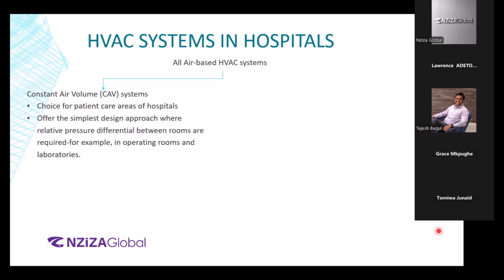The design is very simple. You don't need to have many transitions in the ducts going up and down. The coils are pretty straightforward because it is a constant volume that you'll be pushing through the system, right? And on the other side, we have the variable air volume, right? Variable air volume will be very helpful where you are trying to maintain the pressurization because that will play around with the controls, right?